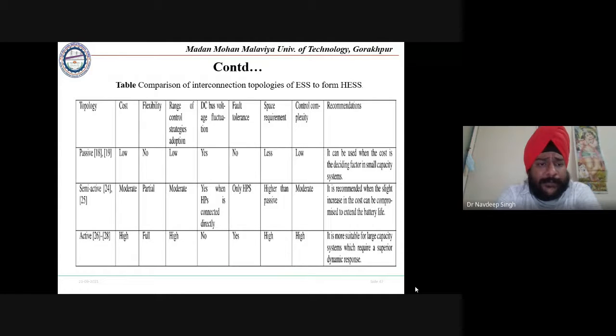It is a fully flexible system with a range of control strategy adoption. If passive is connected to a DC to AC inverter, it is possible, but the control strategy is only for controlling voltage, while fluctuation in the DC supply through the DC link capacitor is very high, so controllability is not possible. Ripples are also there.